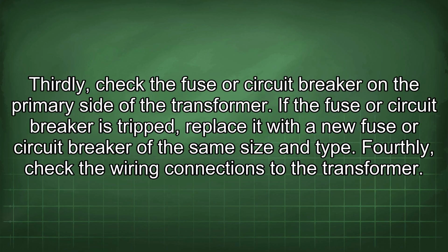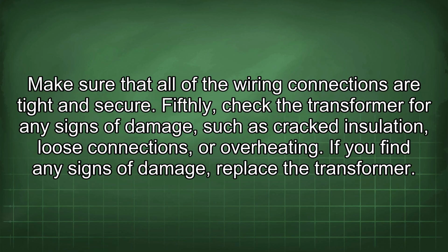Thirdly, check the fuse or circuit breaker on the primary side of the transformer. If the fuse or circuit breaker is tripped, replace it with a new fuse or circuit breaker of the same size and type. Fourthly, check the wiring connections to the transformer. Make sure that all of the wiring connections are tight and secure. Fifthly, check the transformer for any signs of damage, such as cracked insulation, loose connections, or overheating. If you find any signs of damage, replace the transformer.